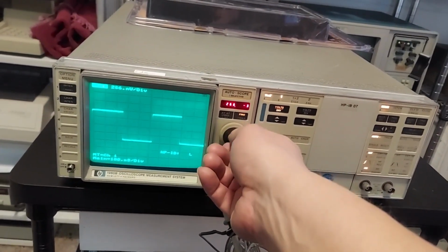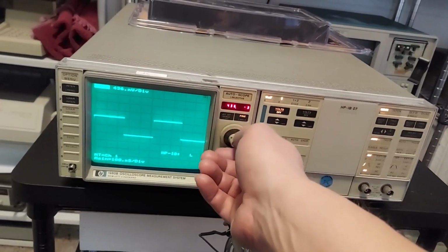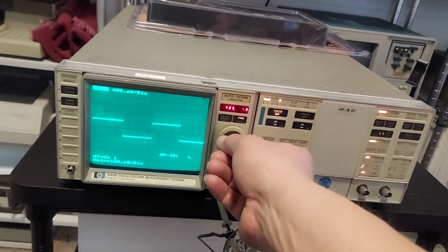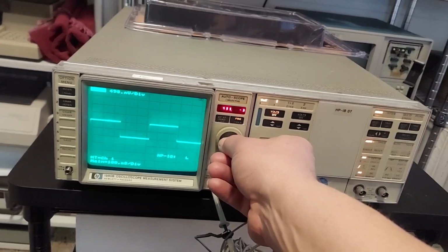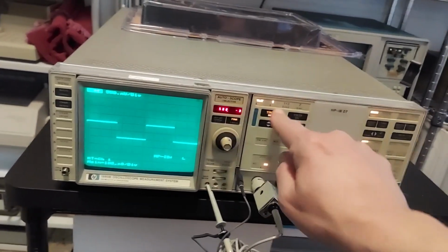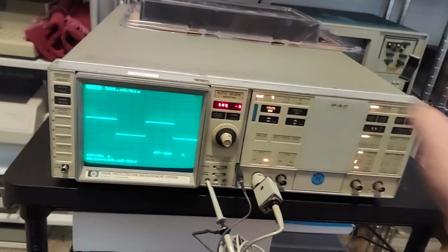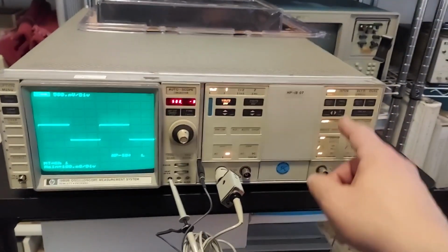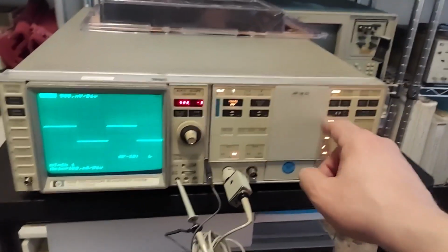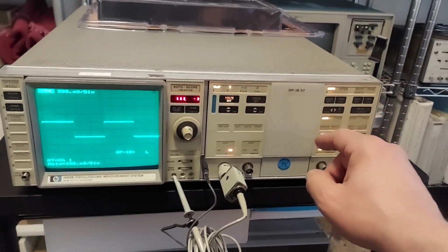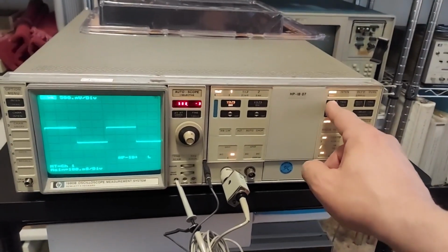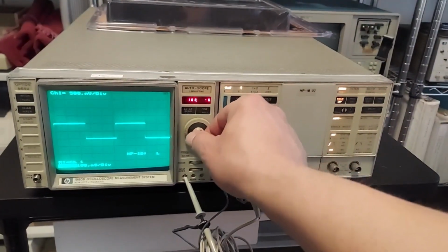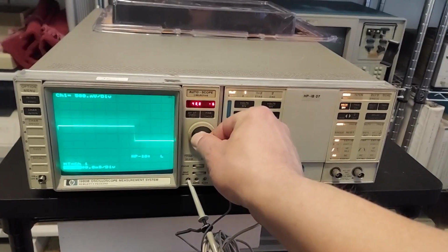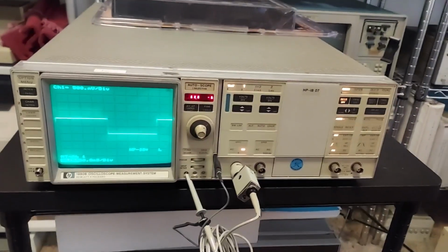Step it in 1 millivolt increments. Same thing with the, go back to that there. Get out of that mode. We can also do the same thing with the trace speed, and speed for, you know, the amount of seconds per division. So we click that button and we can change it that way.